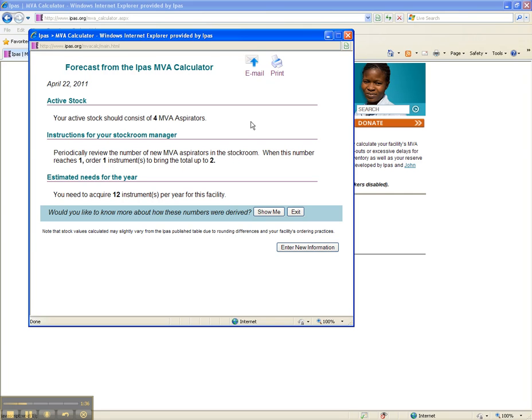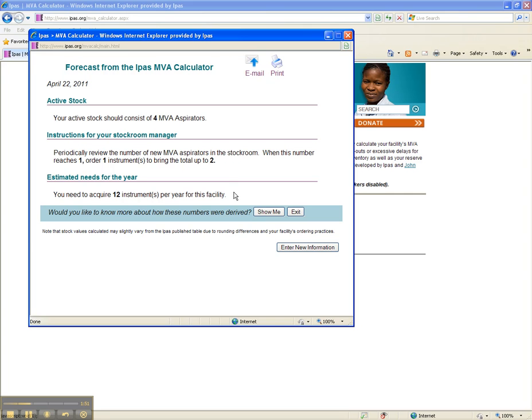Next, you'll see a screen indicating you need 4 MVA aspirators in your active, ready-to-use stock, and that you need to place an order when reserved stock falls below 2. You should also see that you'll need to plan to order up to 12 instruments over the course of a year. The results on this page can be emailed or printed for your convenience.